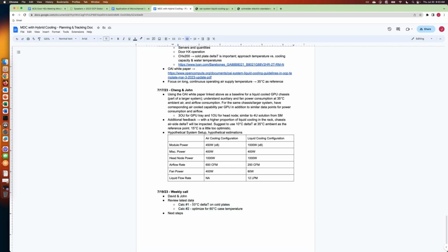One is based on a 10 C delta T on the cold plate loop, which is supported by the white paper. The other is to see if you can minimize the flow rate so you can maximize the return temperature. David wants to look at this from a heat reuse standpoint, and I think Carl is interested in that too.